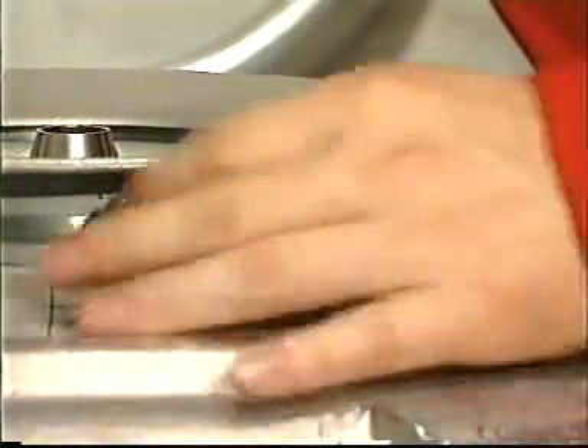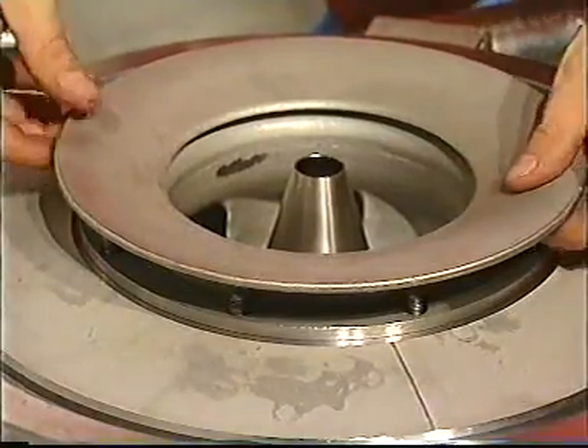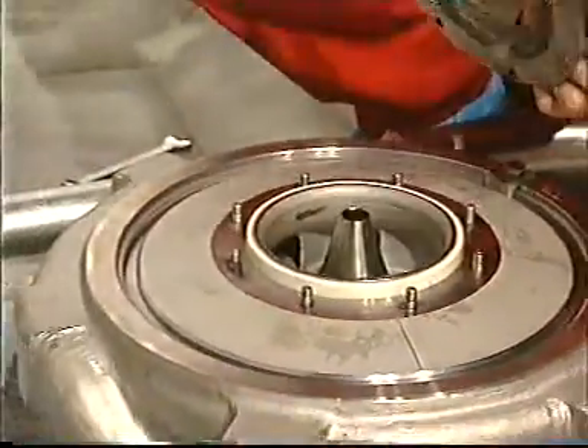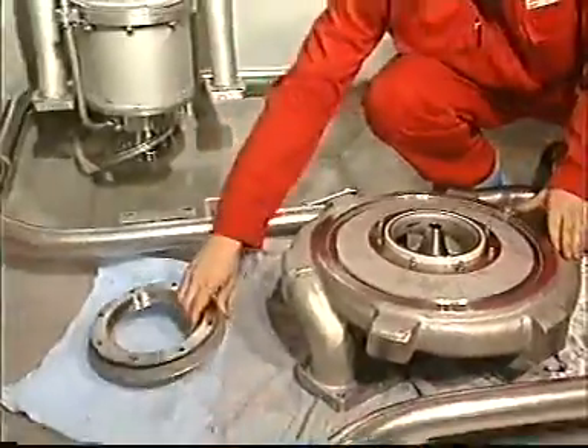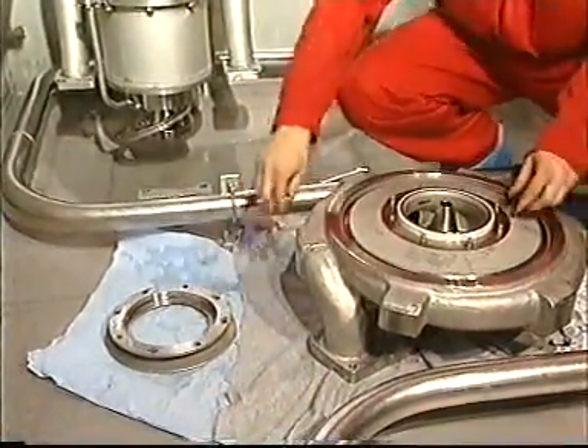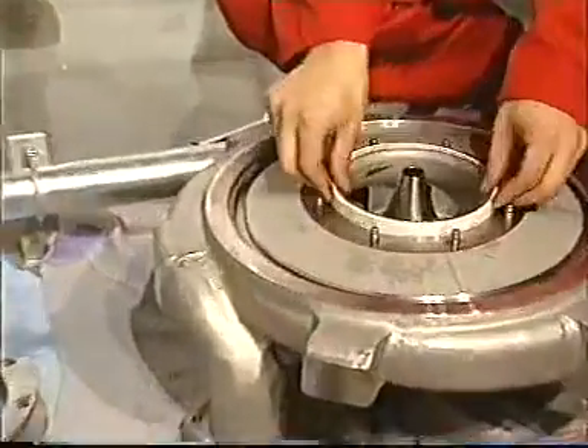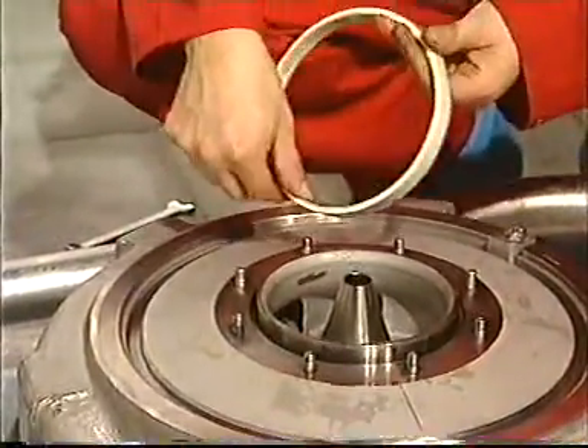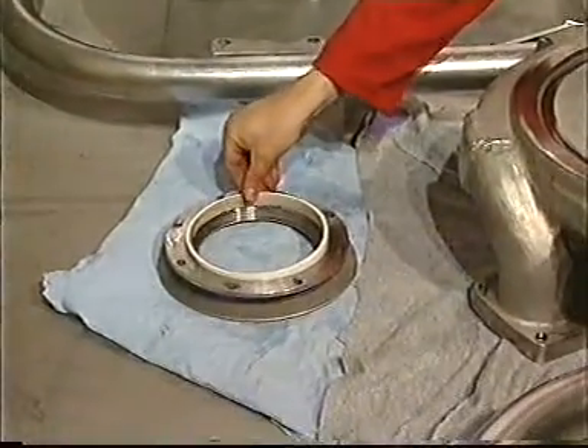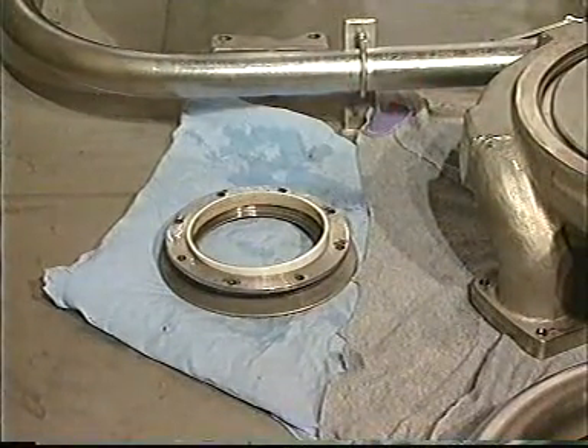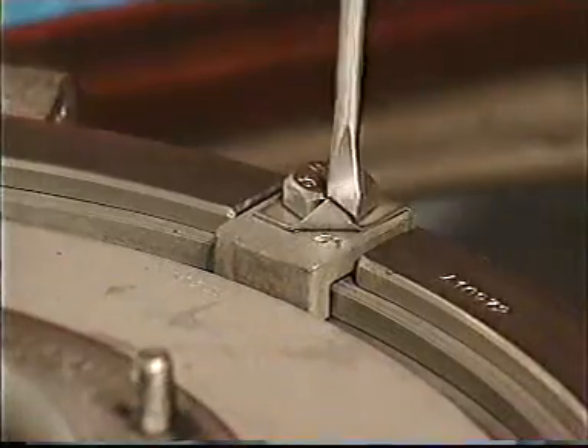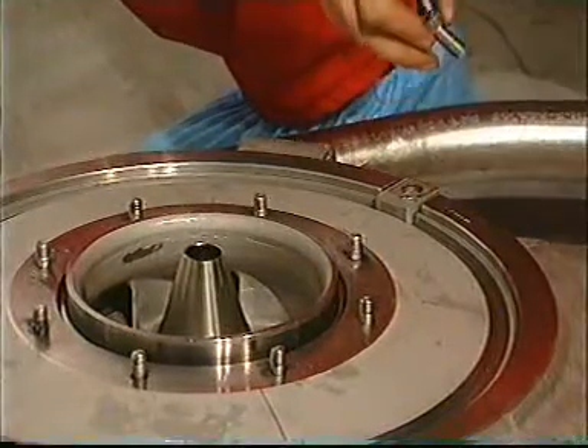The suction cover and the impeller can now be dismantled and the parts can be inspected. Pay special attention to the wear rings. Normal radial clearances when new are approximately 0.2 millimeters. We recommend to change the wear ring if the radial clearance is more than approximately 1 millimeter.